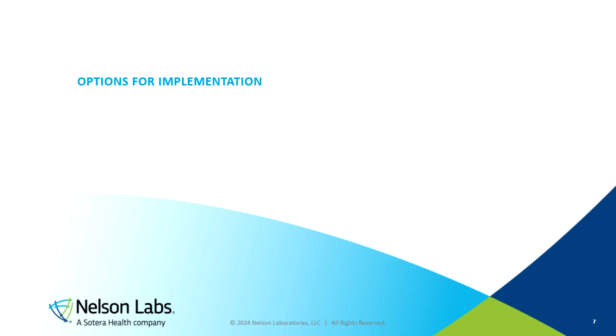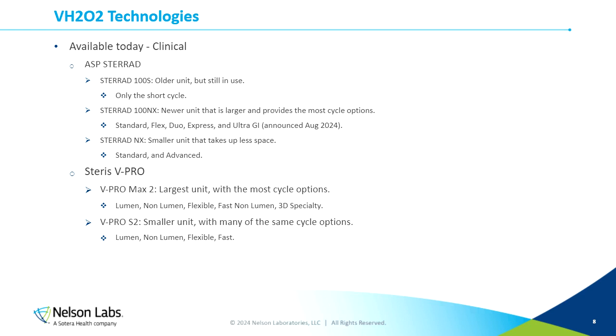So with consideration for implementation and scalability, we need to consider, how are we going to work vaporized hydrogen peroxide into our sterilization? What are our options if we want to move away from one of our other sterilization methods and we want to implement hydrogen peroxide sterilization for our product? So let's talk first about what is available readily today. So first, let's talk about clinical. So when we're talking clinical, what we mean is point of use. This is product that is going to be sterilized at the hospital or at the clinic by the end user. So one of the first options that has been on the market for a very long time is the ASP STERRAD units. So currently for the STERRAD, there are three primary options. So one of the first is the STERRAD 100S.